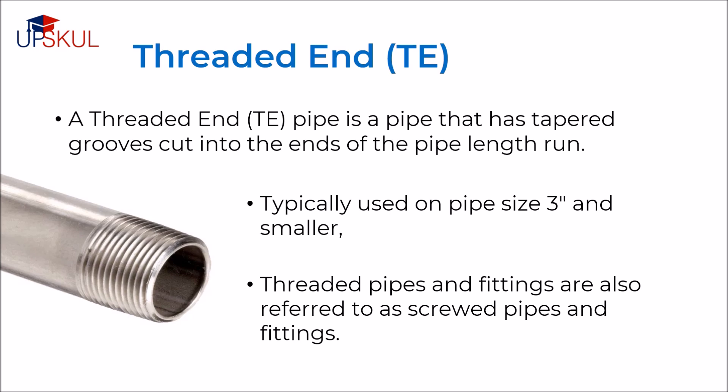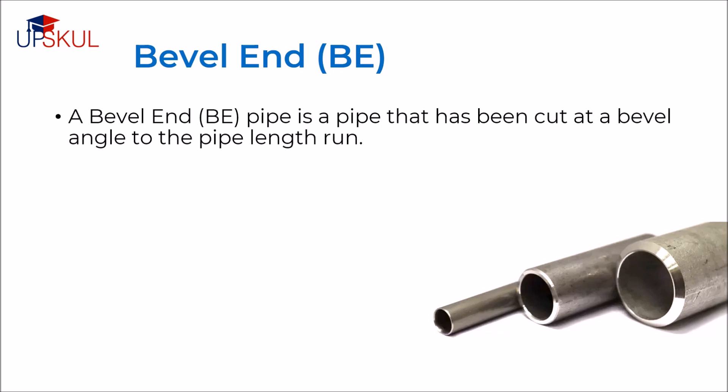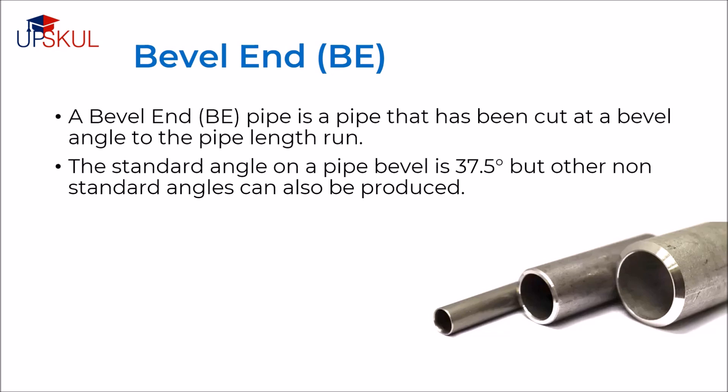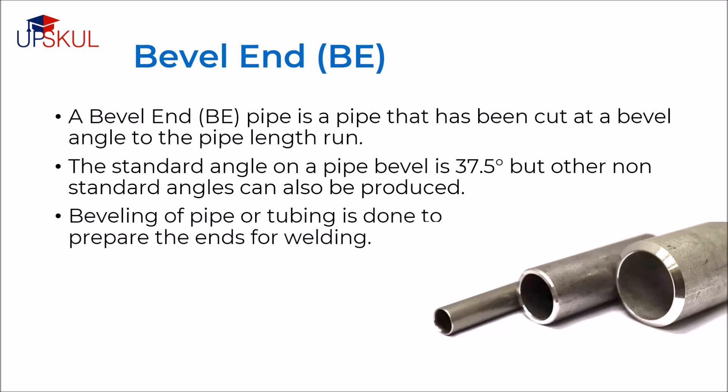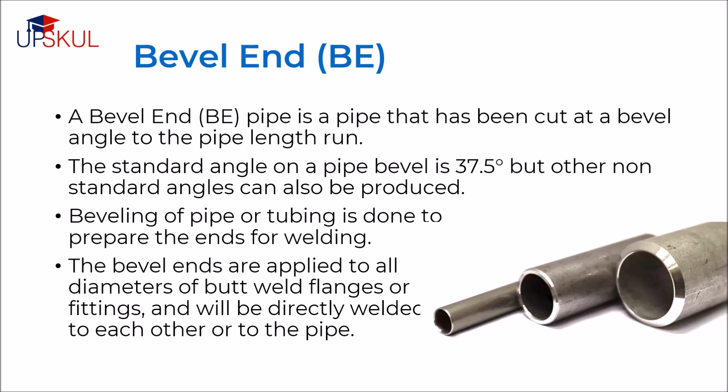Threaded pipes and fittings are also referred to as screw pipes and fittings. They can easily be assembled without welding or other permanent means of connection. Threaded pipes and fittings have threads that are either male or female. Male threads are cut into the outer surface of the pipe while female threads are cut into the inner surface of the pipe. As threaded pipes and fittings are assembled, two pieces are pulled together, and the distance that is pulled together is called the thread engagement. A bevel end pipe is a pipe that has been cut at a bevel angle to the pipe length. The standard angle on the pipe bevel is 37.5 degrees, but other non-standard angles can also be produced. Beveling of a pipe or tubing is done to prepare the ends for welding. Bevel ends are applied to all diameters of butt weld flanges or fittings and will be directly welded to each other or to the pipe.